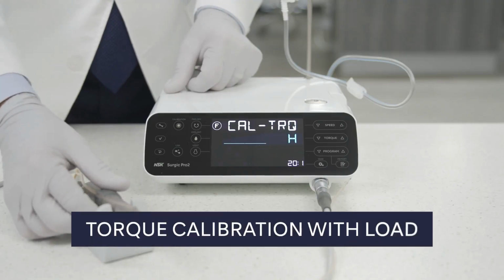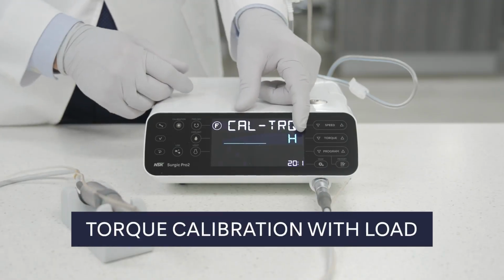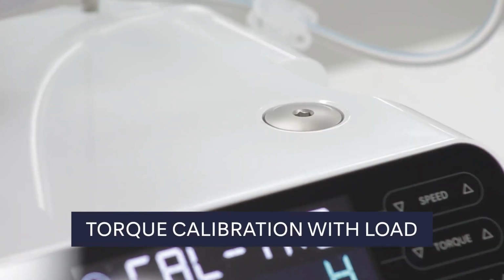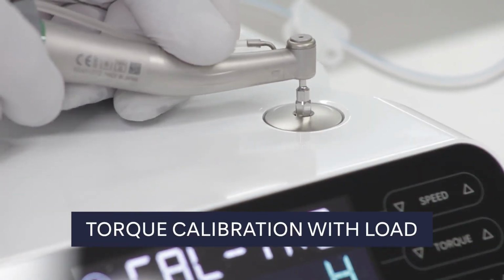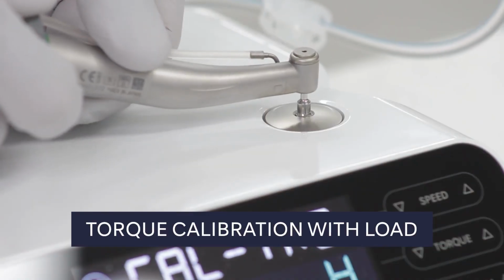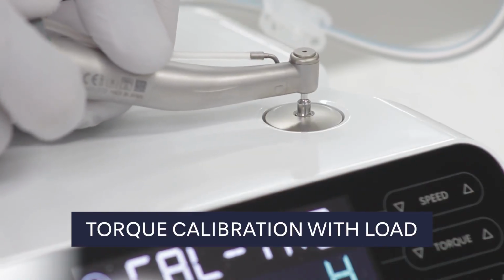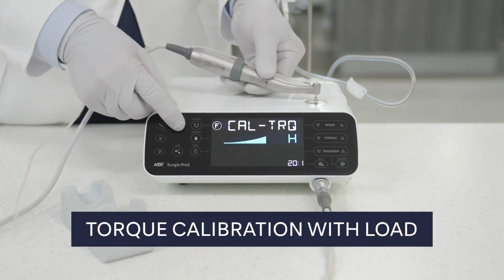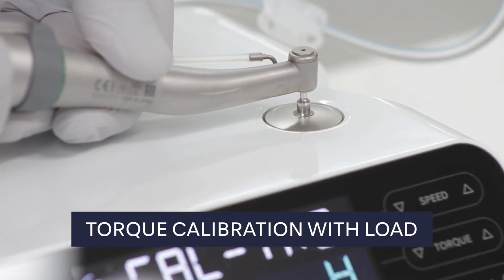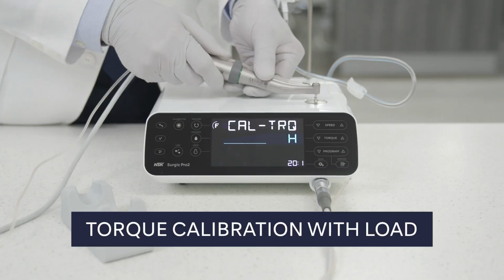For torque calibration with load, an H is shown on the display. Plug the hexagon head of the calibration burr into the calibration block. Hold the motor tightly and vertically without excessive force on the burr. Press calibration, and the burr will begin to rotate the round block rather heavily. Once this part is completed, you will hear a beep and pass appears on the display.